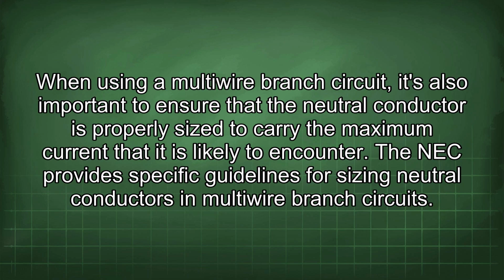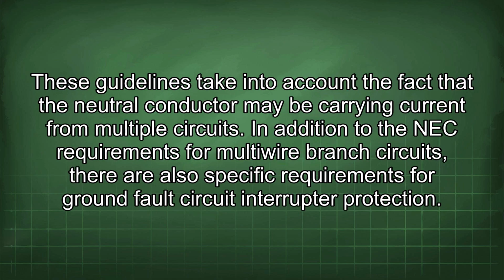When using a multi-wire branch circuit, it's also important to ensure that the neutral conductor is properly sized to carry the maximum current that it is likely to encounter. The NEC provides specific guidelines for sizing neutral conductors in multi-wire branch circuits. These guidelines take into account the fact that the neutral conductor may be carrying current for multiple circuits.